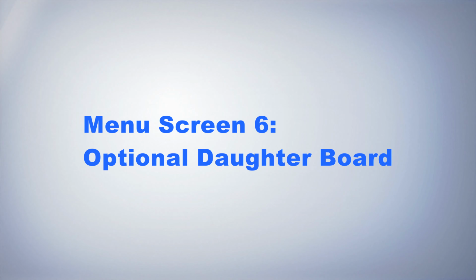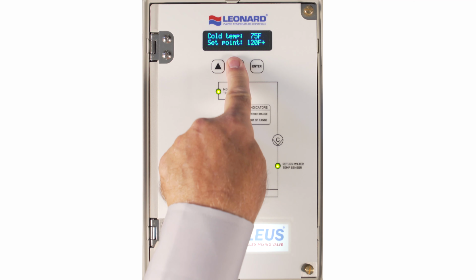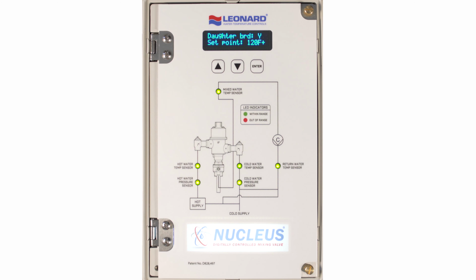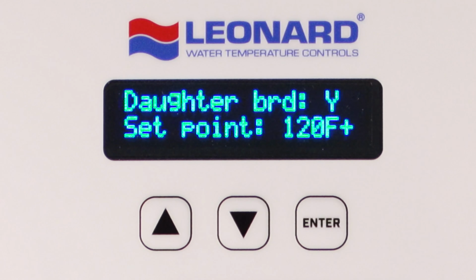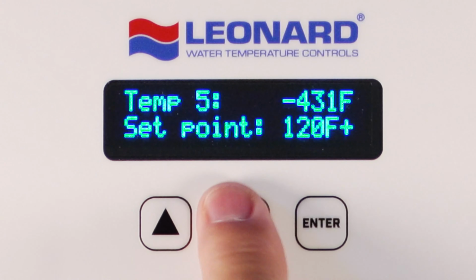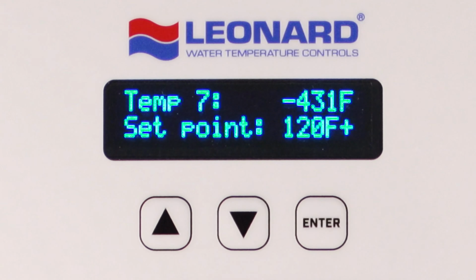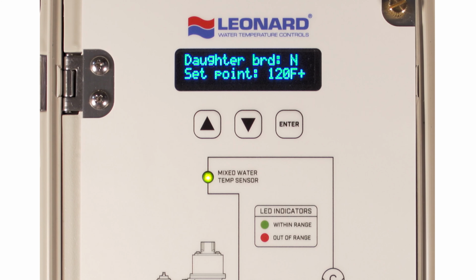Menu screen 6. Optional daughter board. Pressing down 6 times displays daughter board no or yes. This screen indicates whether or not the control box is equipped with a daughter board, which is an add-on optional circuit board for the following additional equipment and capabilities: 4 additional temperature probes, RTDs, T5 through T8, 2 flow meters, F1 and F2, and/or 1 additional pressure sensor, P3, which are standard 4 to 20 milliamp inputs. See O&M manual for details regarding daughter board. Note: if N is showing for daughter board, there will be no additional support screens.